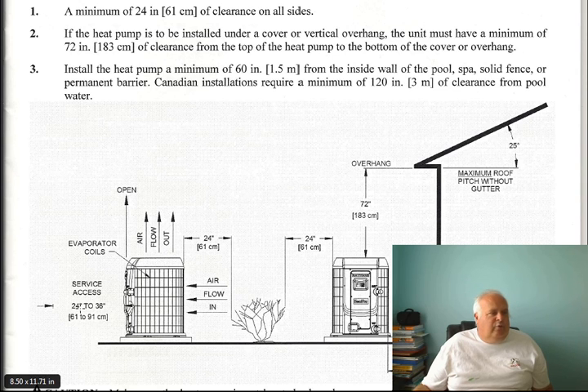Minimum is 24 to 36 inches. These are minimums. You can give five or six feet. This front is your main access point. So you want a minimum of 24 to 36 inches so a mechanic can work on this heat pump.